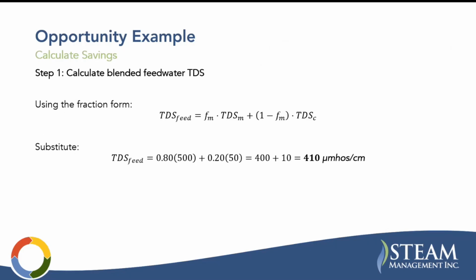Okay, so step one here, we're going to calculate the blended feed water TDS. In this example, we're lucky enough to have those conductivity readings. We have a fraction of makeup water, 80%, times the 500 micromho reading, plus 20% times the 50 condensate return reading. And we're getting a feed water TDS level of 410 micromhos. That's pretty high, I would say. As you can imagine, if this number was 80% and this number was 20%, then this blended TDS level is going to be a lot lower, right? So that's a pretty high feed water TDS level.